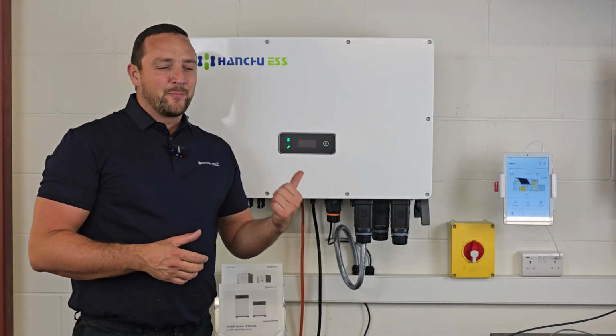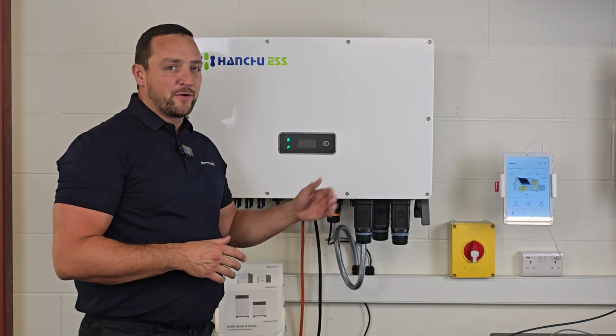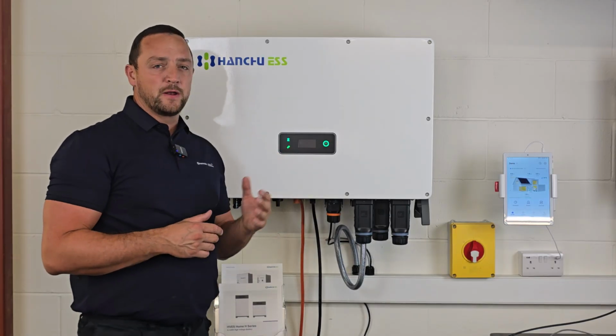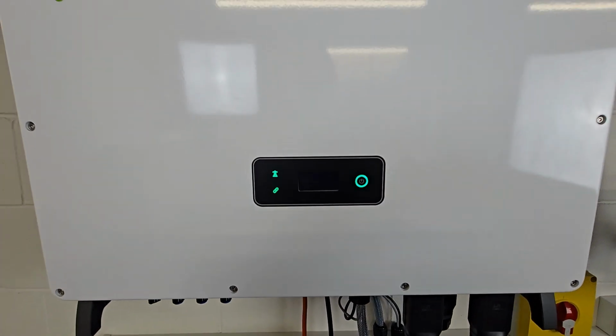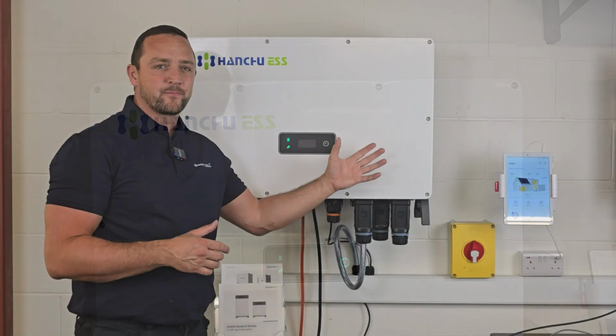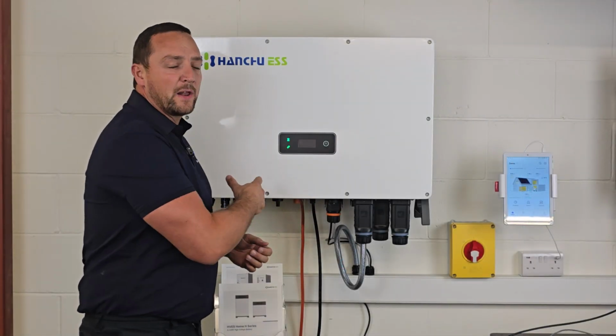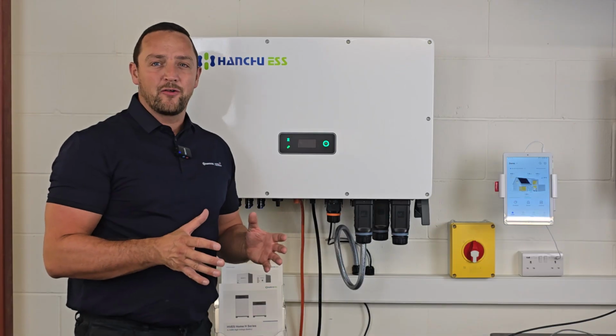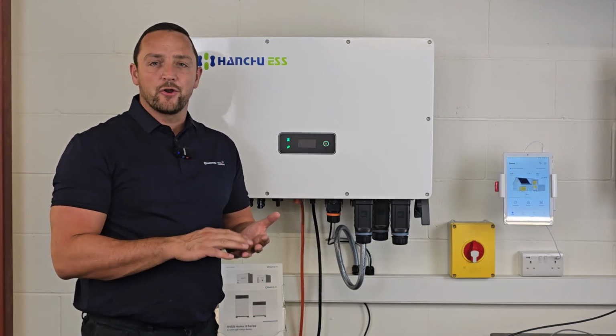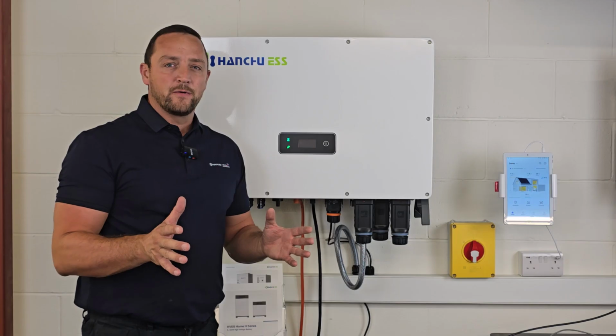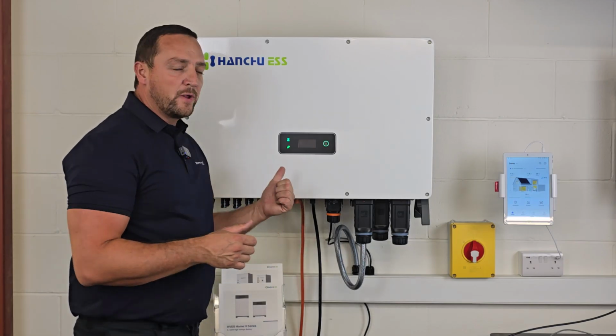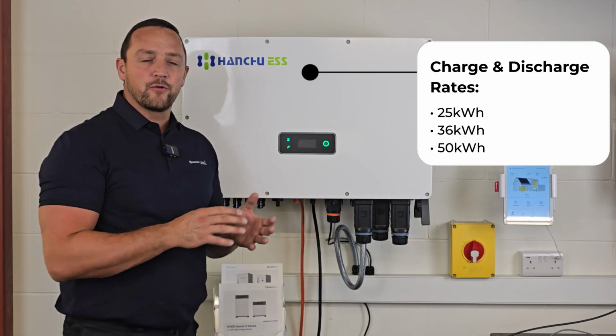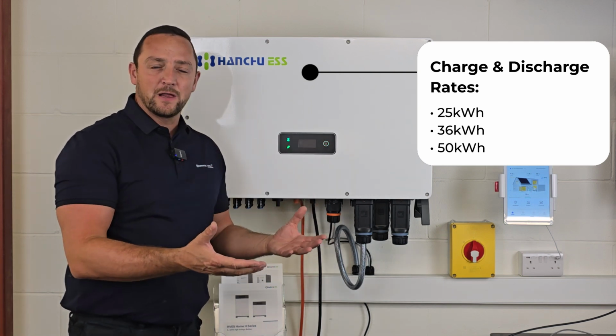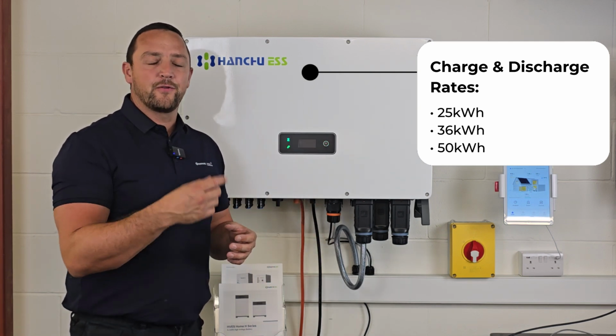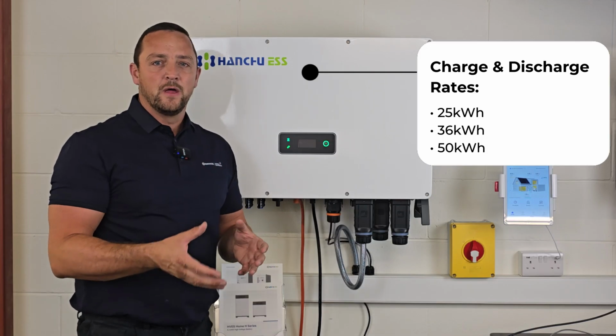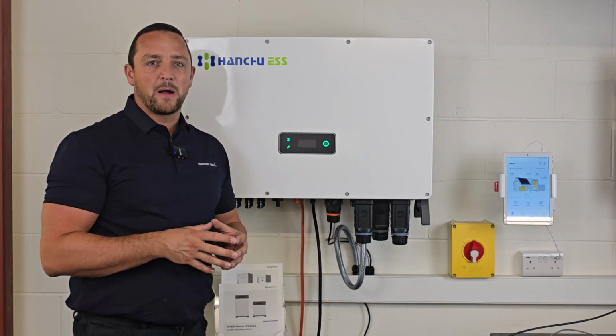So let's now take a look at the emergency power supply that's supplied with every single unit. These units are available in a 25 kilowatt, 36 kilowatt and a 50 kilowatt unit. So in the event of a power cut, this system will actually react within 20 milliseconds, so that will keep up lights on equipment without any form of interruption. Each unit can deliver up to the size of its name, so the 25 can deliver 25 kilowatts, the 36 kilowatts, and the 50 can deliver up to 50 kilowatts of backup power in the event of a power cut.